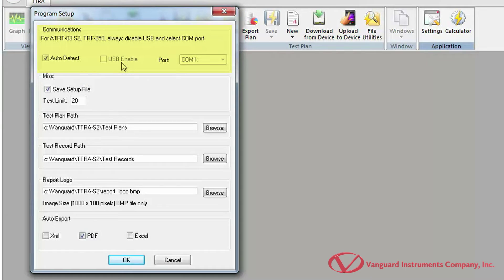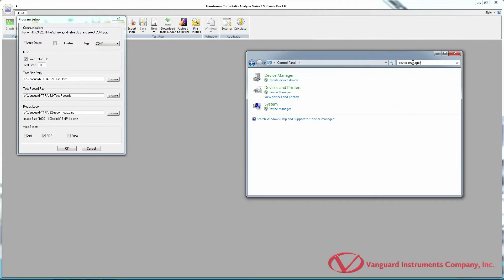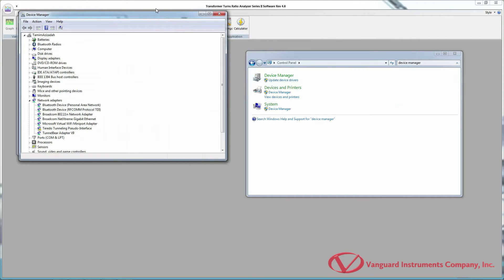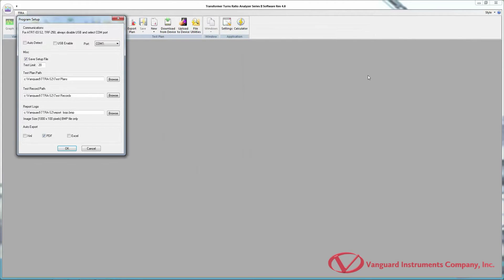The Communications section lists options for connecting your turns ratio analyzer to the computer. In most cases, checking the Auto Detect option will detect the turns ratio tester connected to your computer. If you're using a unit that offers a native USB interface such as the TriPhase, uncheck Auto Detect and check the USB Enable option. If using one of the newer Vanguard units such as the ATRT-03-S2, you can manually select the communication port. First, find the COM port assigned to the device in Windows Device Manager, then select that COM port in the TTRA-S2 software.